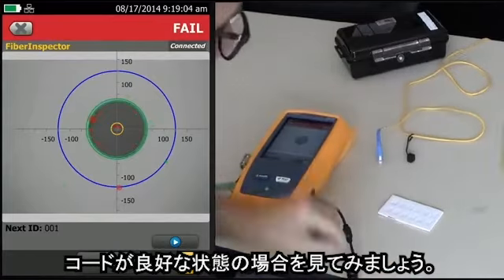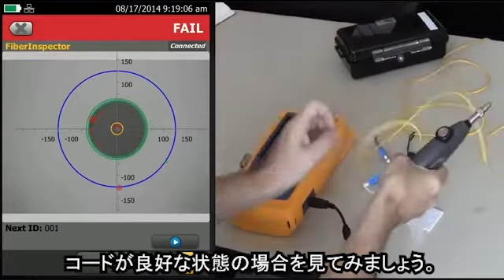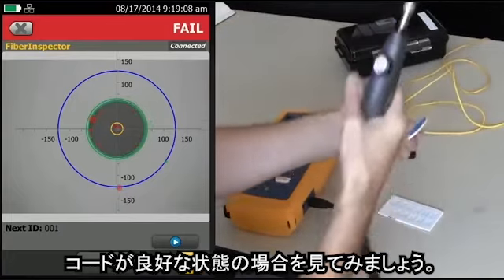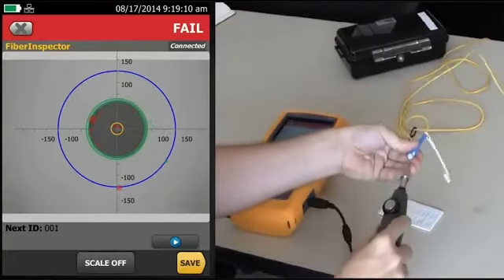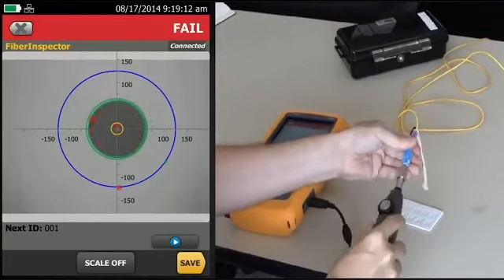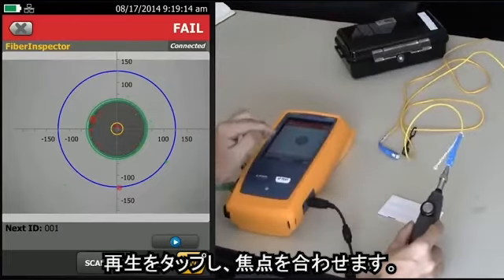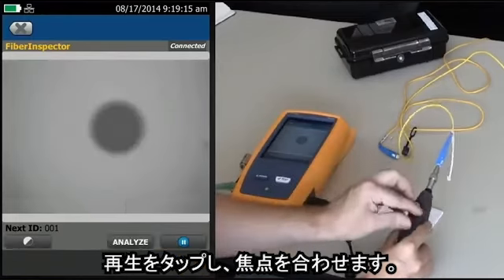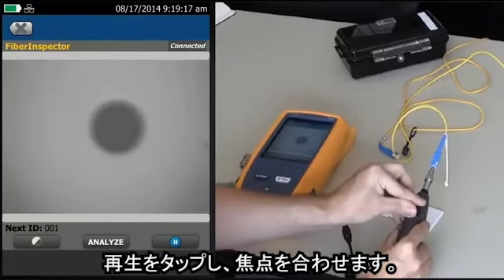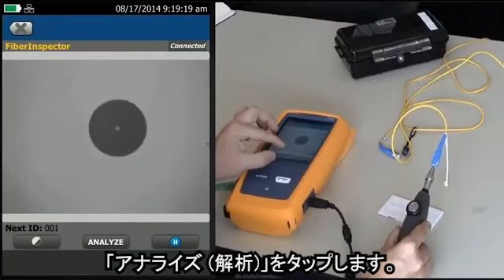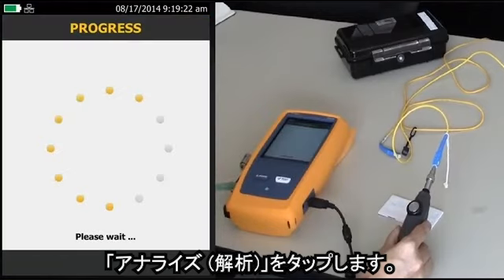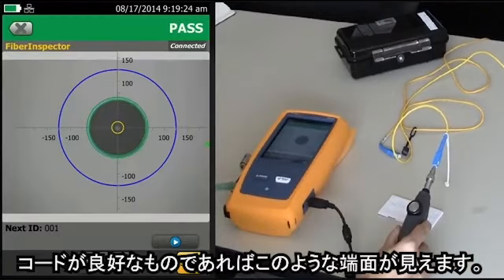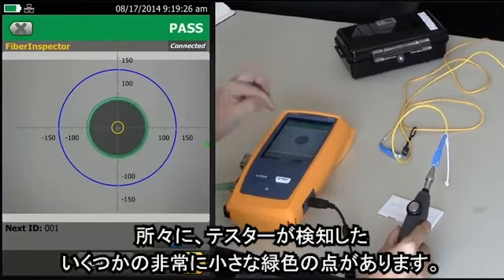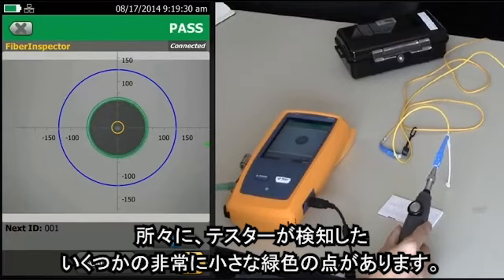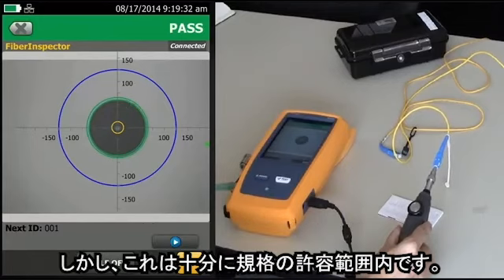When the cord is good, this is what you should see. Play. Focus it in. Analyze. And that's what a good cord looks like. Now you'll notice that there are some very small green dots in there where the instrument's picked up something, but that's well within what the standard permits.